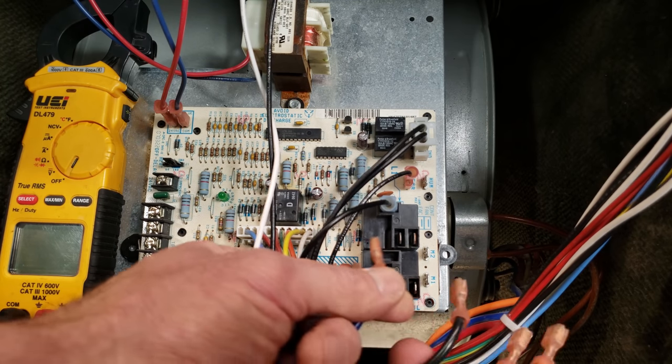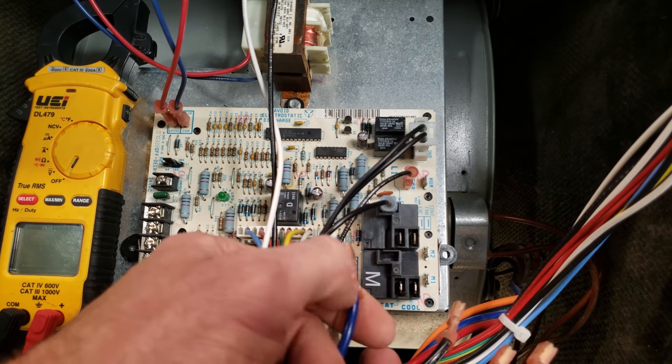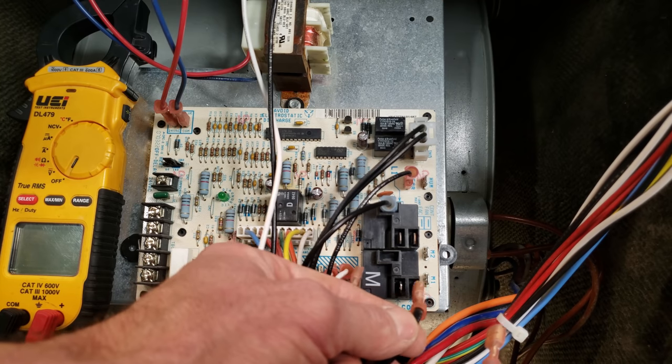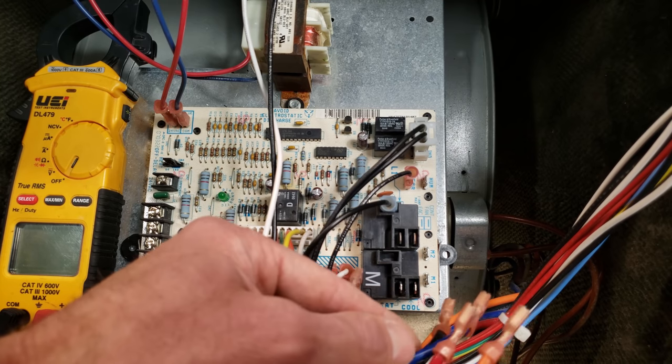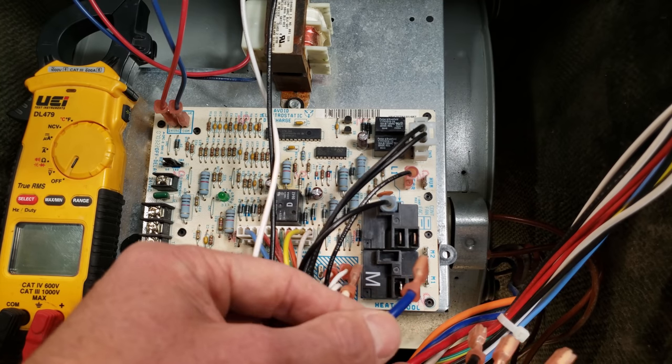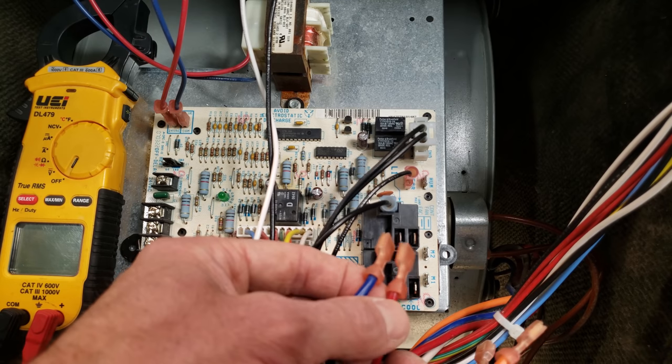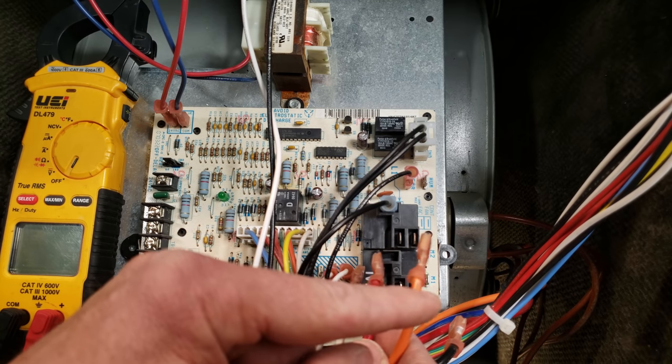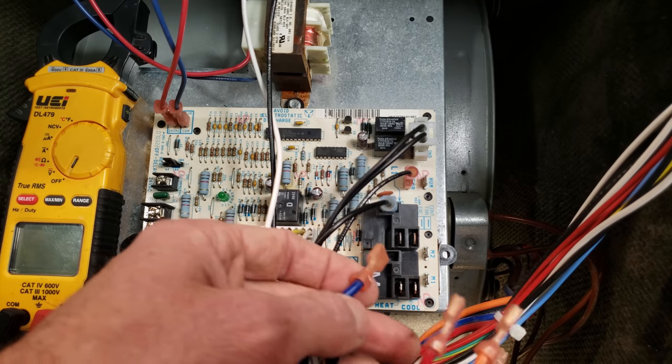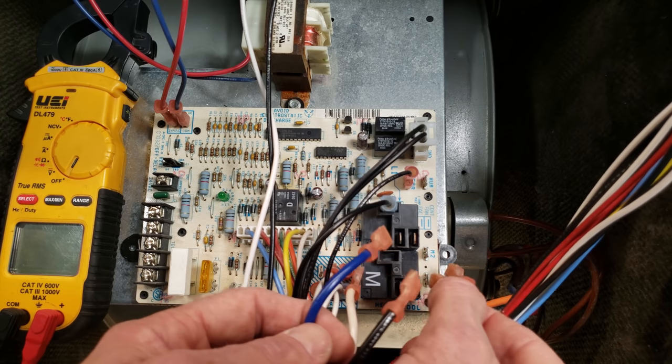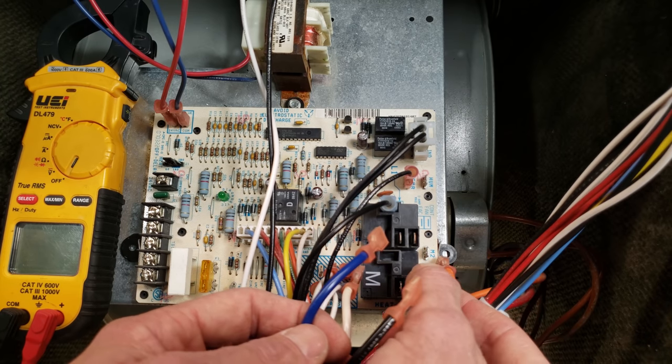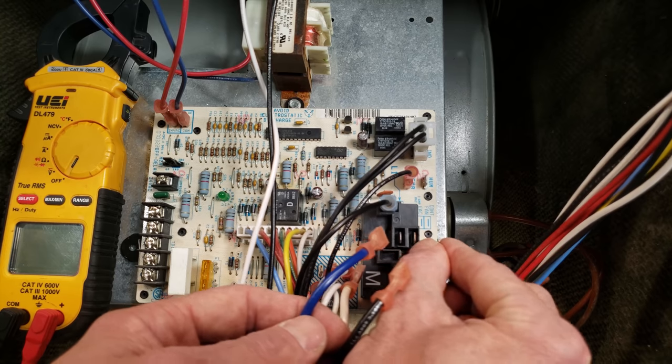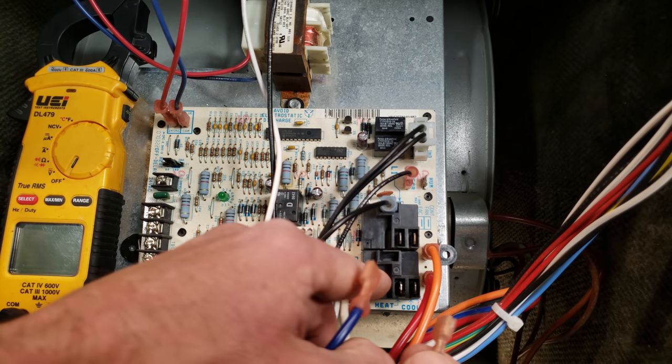In this case and most normally you're going to have your highest fan speed, which is black on your cooling, and in this case blue is your second from lowest speed, red is your lowest speed, and orange is your second from highest speed. So we're just choosing to use our black and blue speeds on this lower relay.